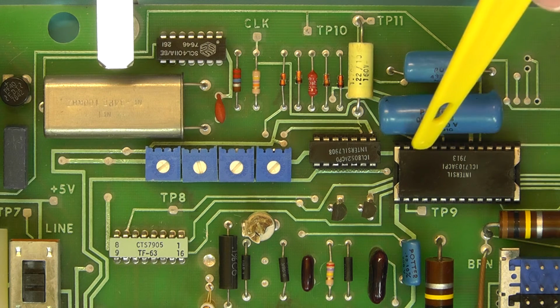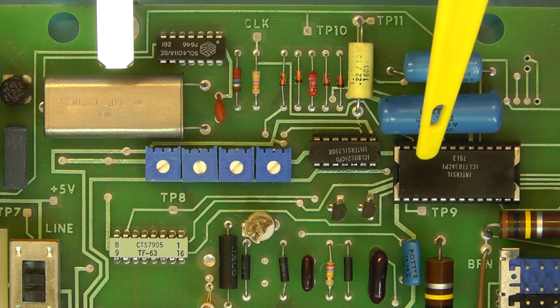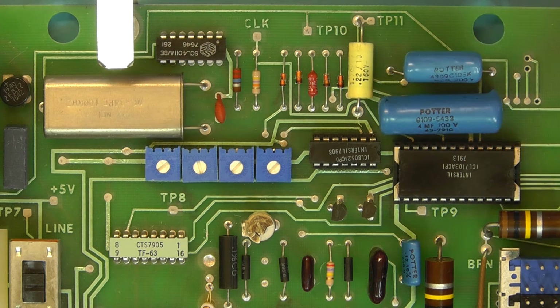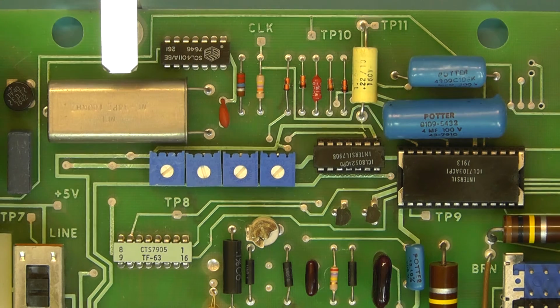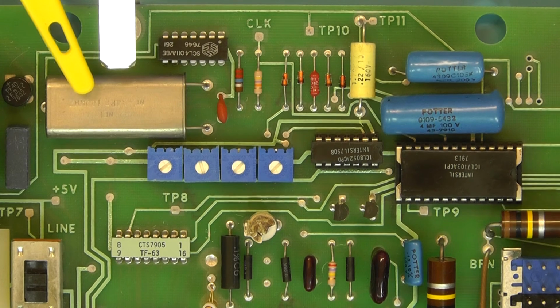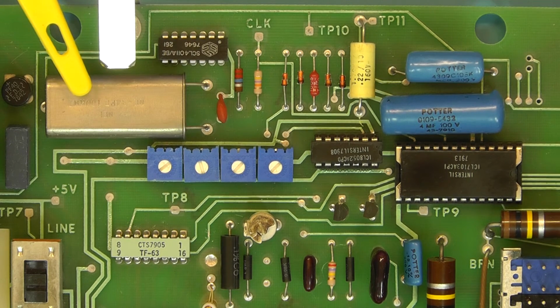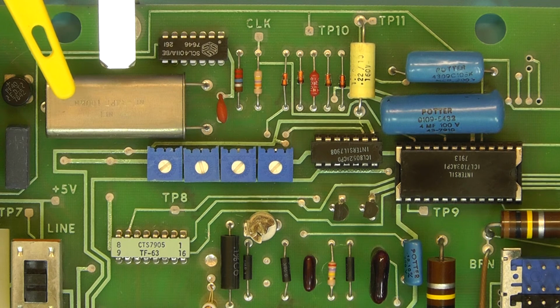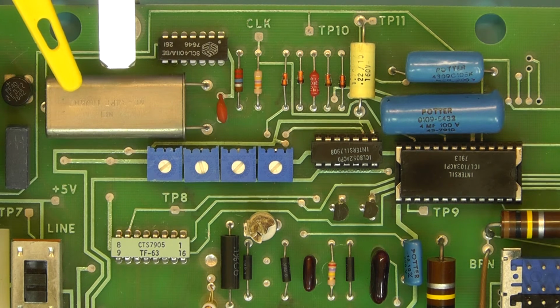The chip itself here contains all the multiplexing, the BCD outputs and the digital drivers for the LED display on the front panel. There's the 100 kilohertz crystal for the clock. The reason Keithley selected 100 kilohertz is that in order to achieve the maximum rejection at both 60 Hz and 50 Hz mains frequencies, they have to have a crystal frequency which is an exact multiple of both those two frequencies, and 100 kilohertz is just that. There are a number of other combinations as well, but they've selected the 100 kilohertz. This allows the meter to do 2.5 readings per second.